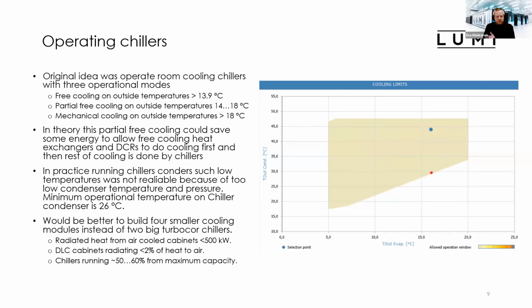So a couple of things then about operating the chillers. We had this original idea from our cooling designers to operate the room cooling chillers with 3 operational modes, as we are doing in the HPC cooling. So free cooling when outside temperatures are below 14 degrees, then partial free cooling from 14 to 18 degrees, and mechanical cooling only over 18 Celsius degrees. In theory, this partial free cooling could save some energy by allowing the free cooling heat exchangers and dry coolers to do the cooling first, and then the rest of the cooling is done by the chillers. But in practice, running the chiller condensers at such low temperatures is a problem, because if we are using the free cooling, the temperatures going into the inlet side of the condensers of the chillers are too low.